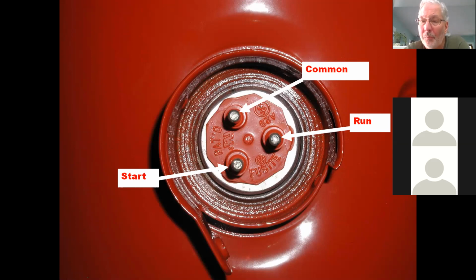Because when you put a vacuum in a compressor, it changes the insulation value based on the atmospheric pressure. And you could have a lightning storm in there and you could burn out a compressor and blow the plug out. But with the charge in the compressor, I don't think it's going to be an issue.